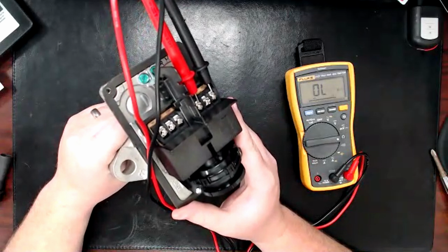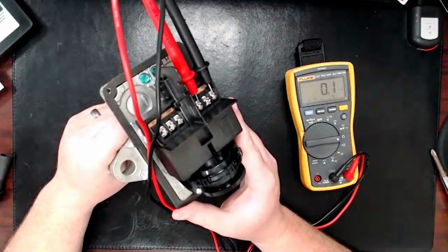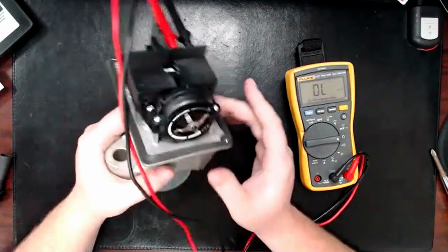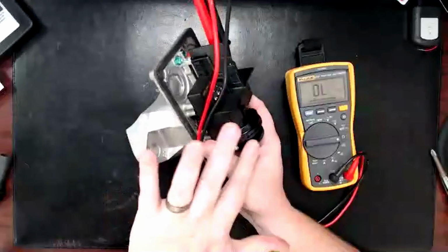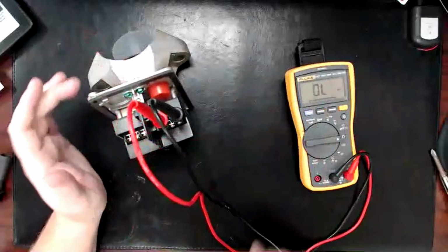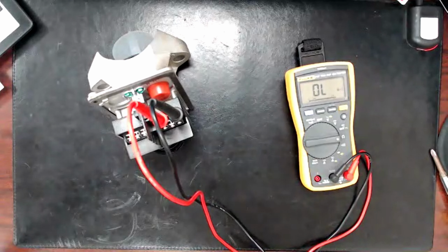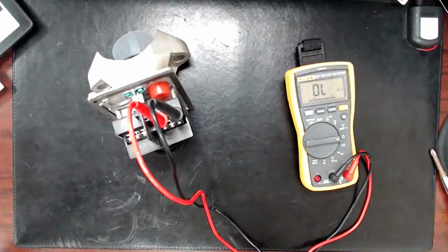I don't know how long I have this set for. There we go, it switched. And so that's what the time delay is for, so that you don't get false alarms from things like changing water pressure. Water pressure can also change if there's dramatic temperature changes. Just like your car's tire pressure, sometimes you got to air your tires up on your car whenever the temperature drops too much. Water changes the exact same way that air does in that situation.